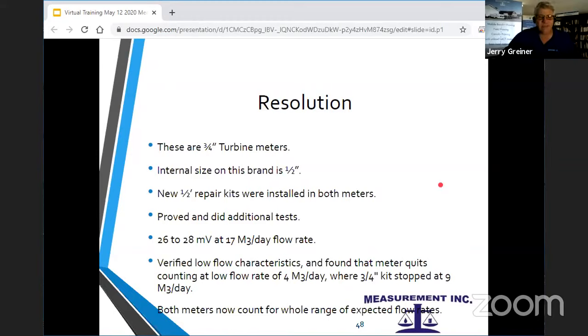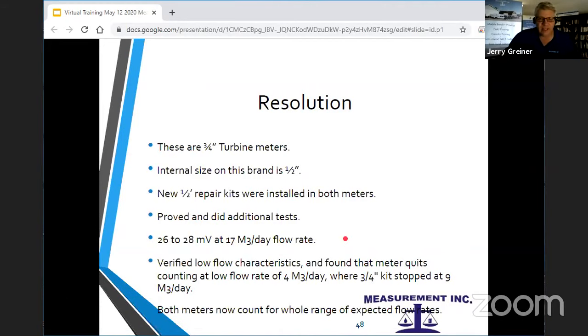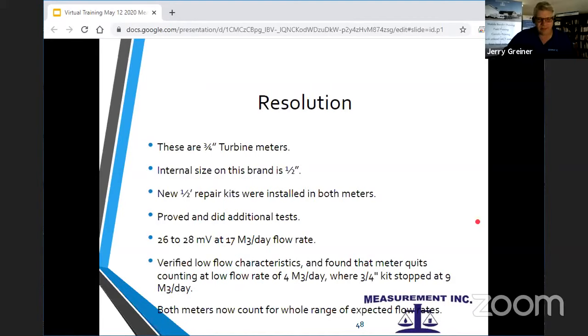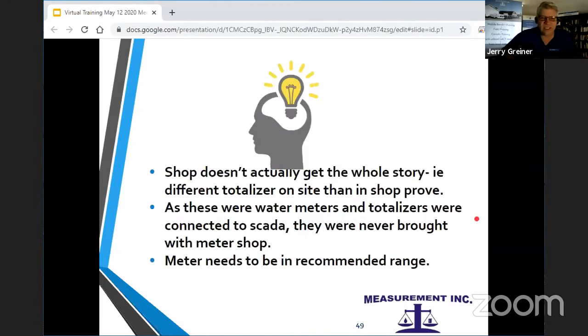We did some additional proofs. We found with the 1/2 inch kits, they spin a lot quicker. It makes an output of 26 to 28 millivolts, and they counted right down to a rate of 4 cubic meters per day, where the 3/4 inch kits stopped at 9 cubes a day. These counted right down to 4 cubic meters a day. They counted all the way through. And so what we learned is the shop didn't get the whole story here.